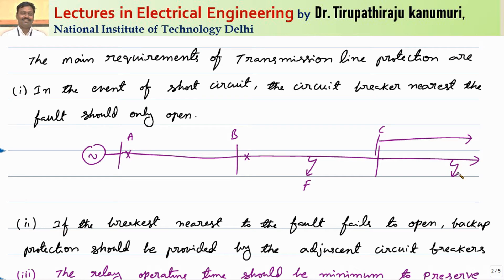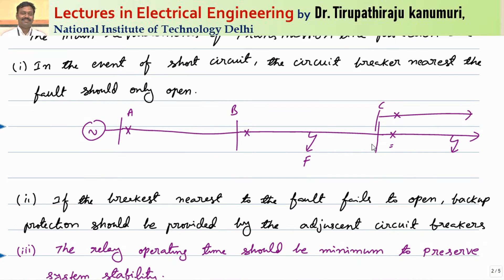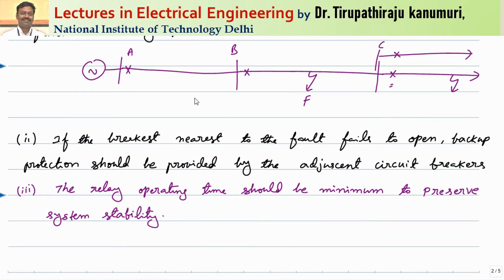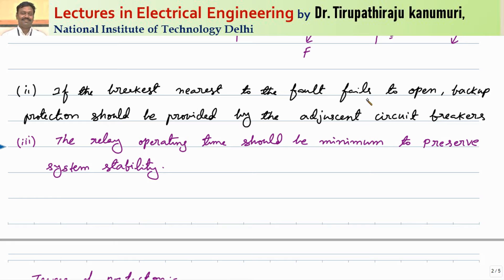If the circuit breaker at B does not operate, then only as backup should the circuit breaker at point A operate. Similarly, if the fault happens at another point, the nearest circuit breaker should operate first; if that does not operate, the circuit breaker at point B should operate; and only if that also fails should A operate. This ensures only a small part of the system is disconnected without affecting system stability. Backup protection is always required.